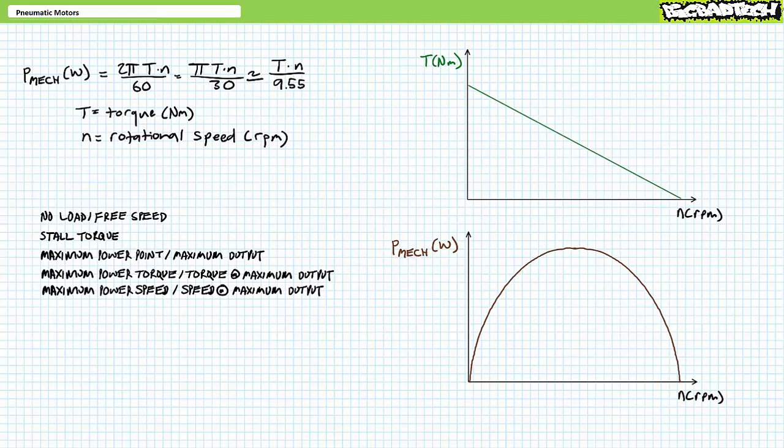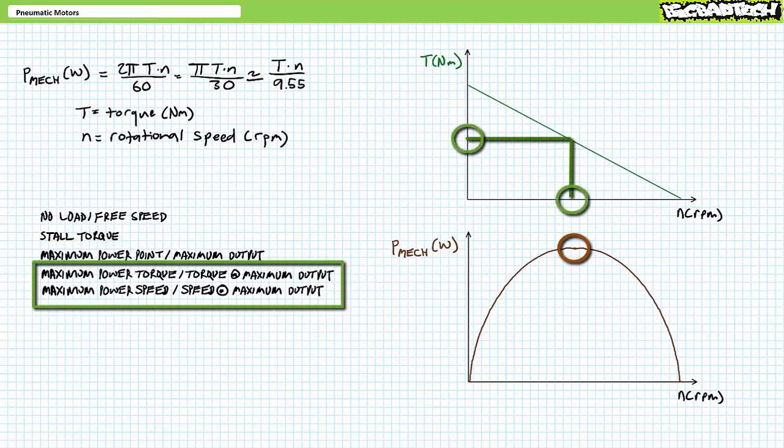Several points of interest can be found on an air motor speed torque and mechanical power curve, notably the no load or free speed, the stall torque, the maximum mechanical power point, and the maximum power torque and the maximum power speed. As implied by the title, the no load or free speed is the speed of the shaft when exerting no torque. This is the far right of the speed torque curve. Again, as implied by the title, stall torque is the torque exerted by the motor when it comes to rest from a running condition. Similarly, the maximum power point or maximum output is the peak of the power curve, which typically occurs around 50% of the free speed. The maximum power point is characterized by maximum power torque and maximum power speed. These properties alternatively might be called torque at maximum output or speed at maximum output depending upon manufacturer.